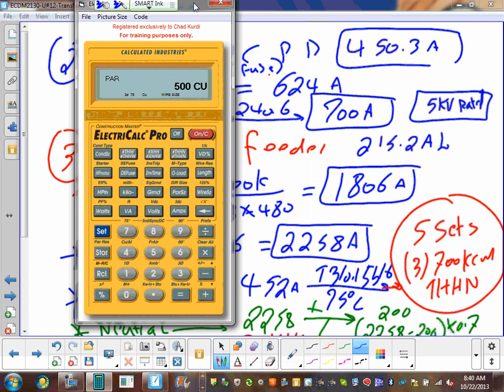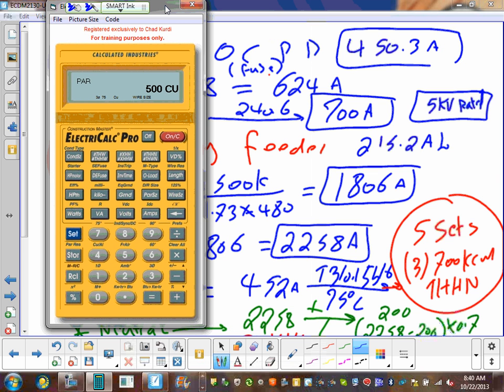5 sets. Why did I come up with 700 here? It's sizing it based on 500 kcm. Interesting. 5 sets, 500 kcm. Well, I don't know if they take into consideration, sometimes when you put them beside each other, 5 sets, you can't use the table directly, you have to go to other tables. This is an extreme case where you're paralleling. You might have to check your work, but it came up with 500 kcm.